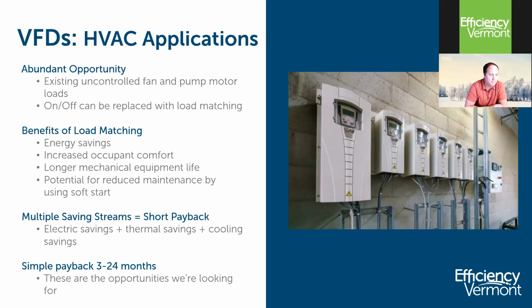Benefits of load matching, we're in the energy savings business, so that's our driver here. But there's other benefits to using drives. You've probably all been in a room where there's excess airflow, and at any given temperature, excess airflow is going to make the room feel cooler, sometimes too cool. And that's probably because the air handler or the rooftop unit only has a single fan speed, so it's blowing constant. And if it's not matched properly to the space and wasn't balanced properly with dampers, it's going to blow excess air. If you're holding back fans with dampers, you're making that fan work harder just to do a part load job. That's where the VFD can really shine. Slow the fan down, you can open the damper back up, you take a lot of load off that fan and you save a bunch of energy.